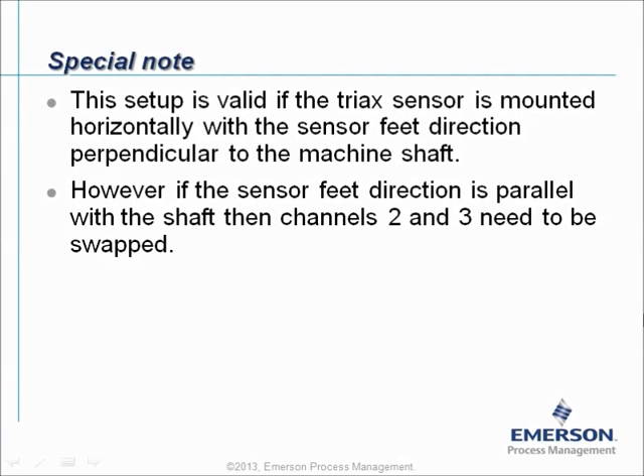Special note: this setup is valid if the Triax sensor is mounted horizontally with the sensor feet direction perpendicular to the machine shaft. However, if the sensor feet direction is parallel with the shaft, then channel 2 and channel 3 need to be swapped.